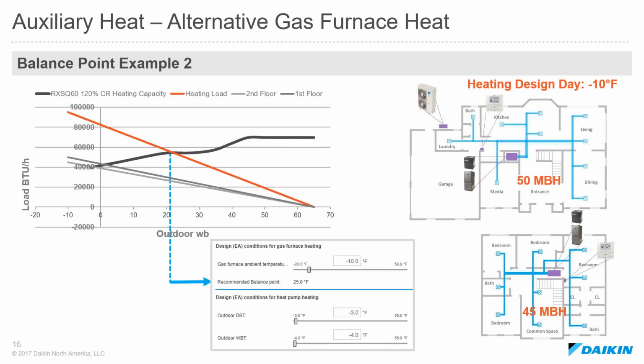Here's another example, except now we're looking at something that's outside of the design day temperatures, outside of our operational envelope on the heat pump. So it's -10 degrees. VRV systems heat pump heating is supported down to -4 degrees. Doesn't mean it's going to lock itself out at that, but the supported operational envelope is -4. So in this case, we have a heating load of 50 downstairs, heating load of 45 upstairs. The total load line is going to be 95, and that's occurring at -10 degrees outside. And we're going to get a balance point temperature of 25 degrees in this case. So you see 21 degrees, again, we rounded up, and it's 25 at the point that we would switch over.